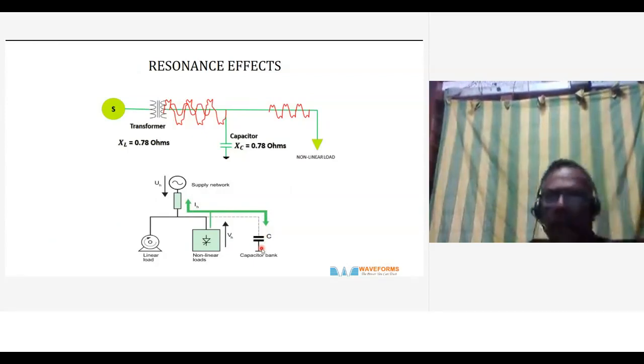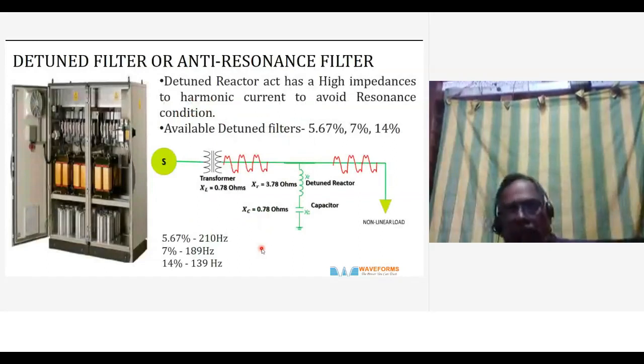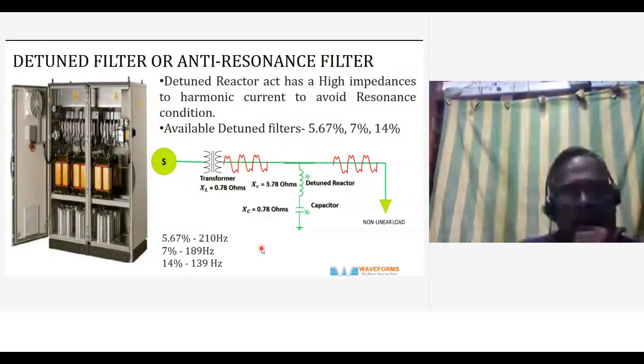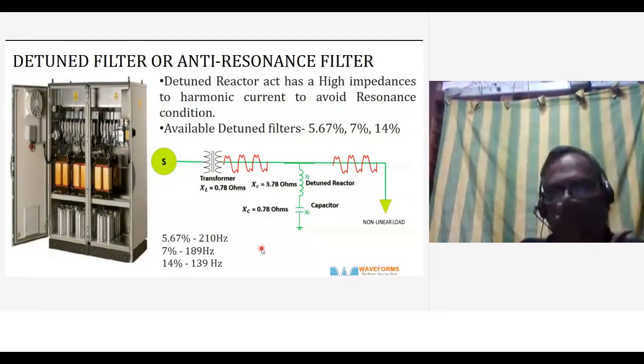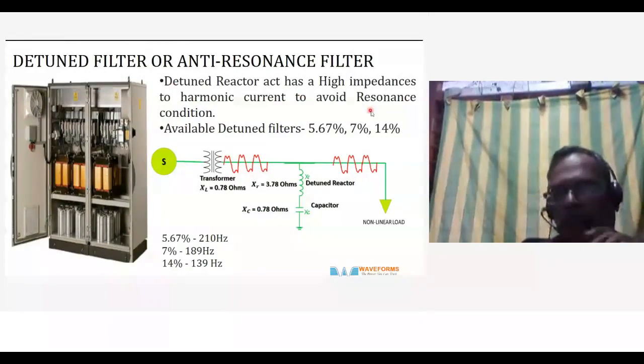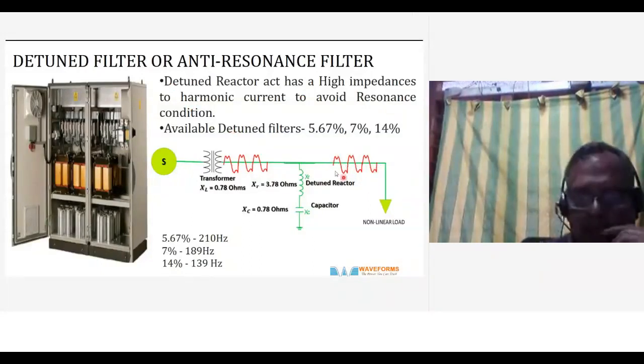This resonance effect is there in a lot of installations because due care is not taken about the harmonics. To solve this, they use detuned or anti-resonant filters in series with the capacitor. This detuned reactor acts as a high impedance to harmonic current to avoid the resonance condition. If there is a fifth harmonic, you will have a 7% filter, which is about 189 hertz, and 189 hertz is away from 250 hertz. So they act as a detuned filter. They act like a block. They block the harmonics into the capacitor.